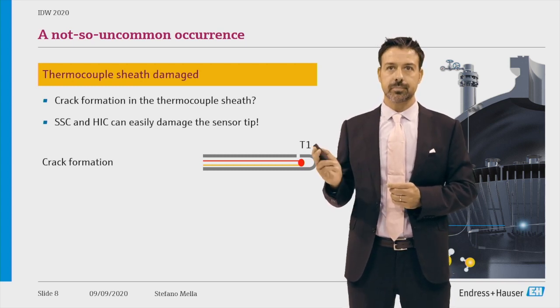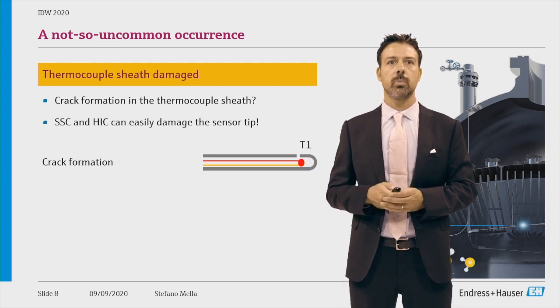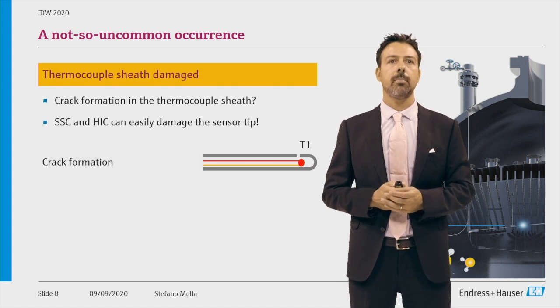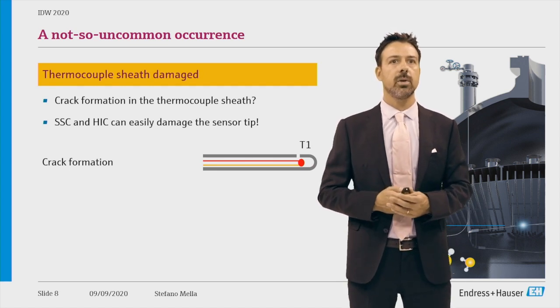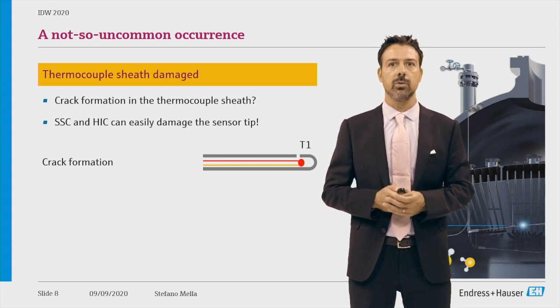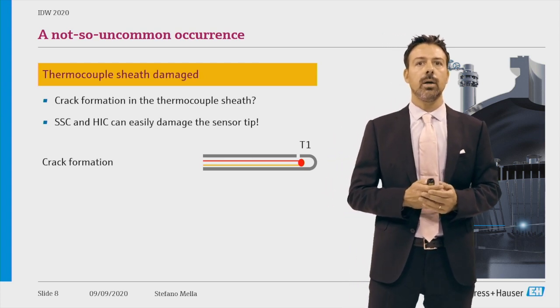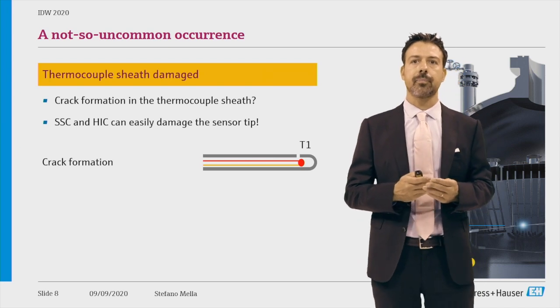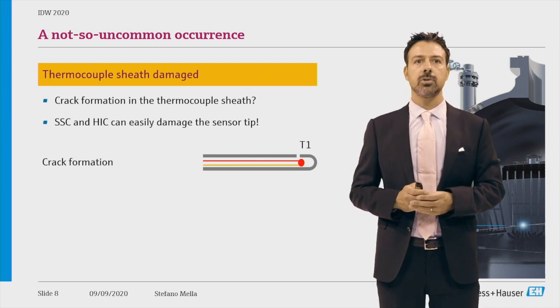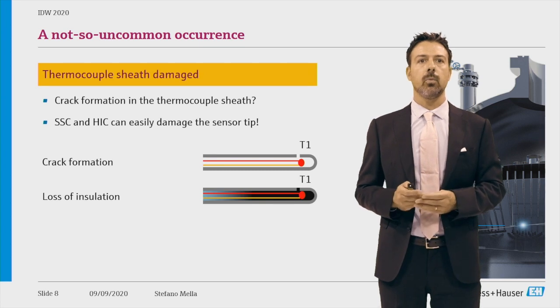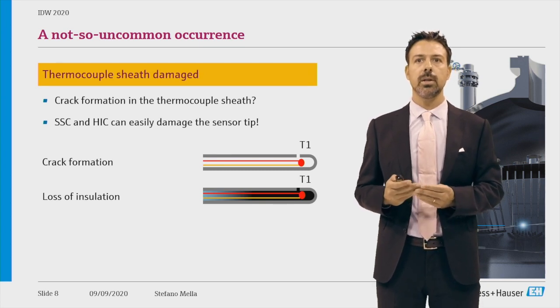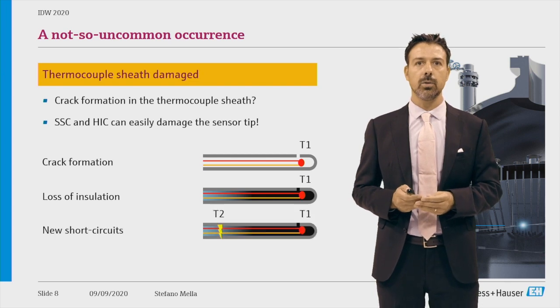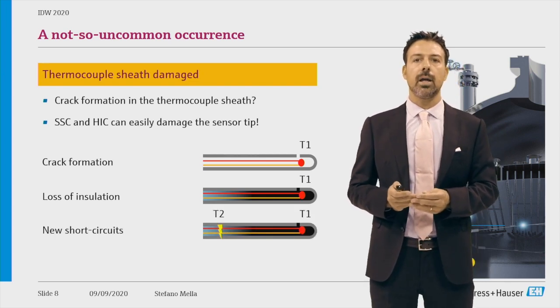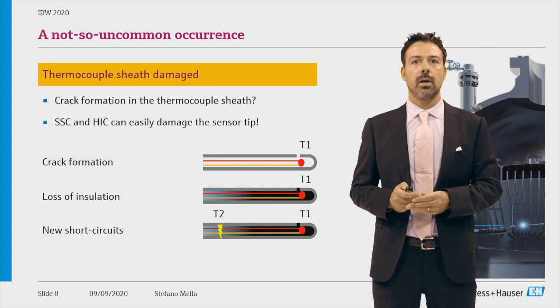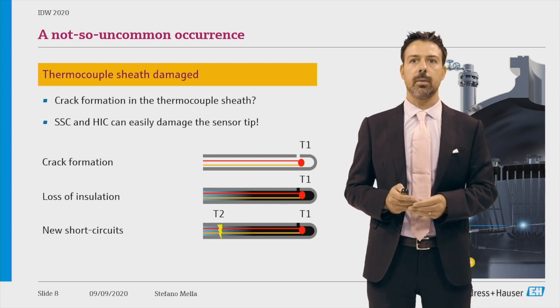Here you might see there is a small white area close to T1 which represents a crack, and the crack can happen because of many phenomena like stress corrosion cracking or hydrogen induced cracking. So when a crack happens on the thermocouple sheath, then immediately we have a loss of insulation. In other words, the mineral insulated powder gets polluted and also contaminated. And when it happens, new short circuits and new hot junctions might happen on the thermocouple.